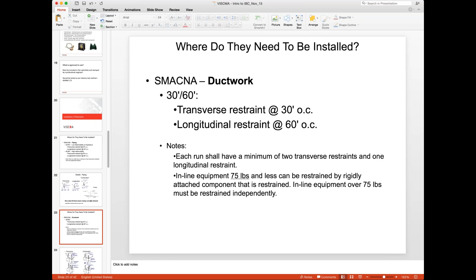And here's the same 4 layouts as for the piping before. And so rather than go individually through them, one thing I do want to point out that's important, a lot of people don't realize, if you look, probably that's best on the lower 2 drawings, the transverse bracing doesn't technically have to span outboard of the ductwork. They can cross inboard, so they don't run into other pipes, other ductwork. You still run it at the same roughly 45 degrees off the horizontal, and you have a lot easier installation. So for the contractors out there, you may only see them on the drawing where they splay outboard, but you can go inboard if you have the room. Much less interference.